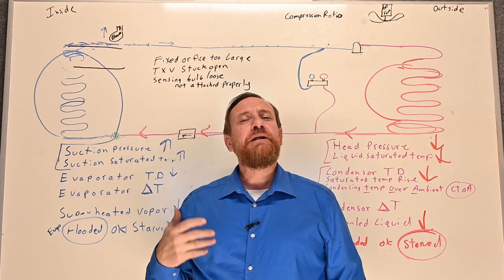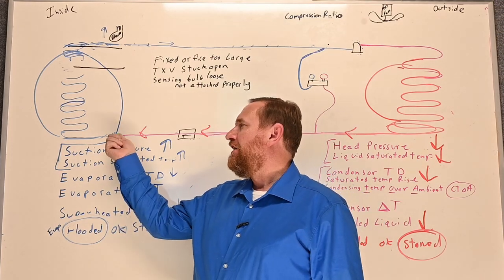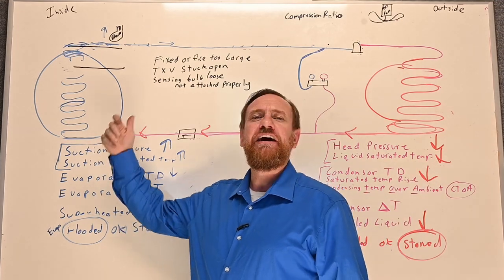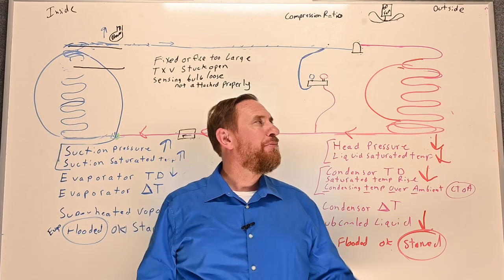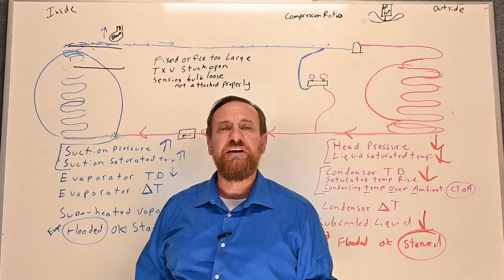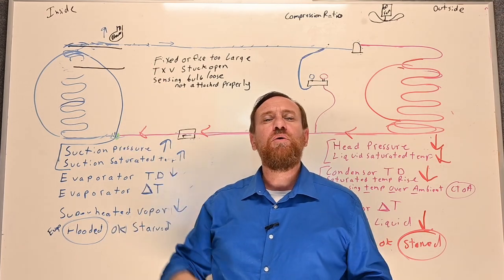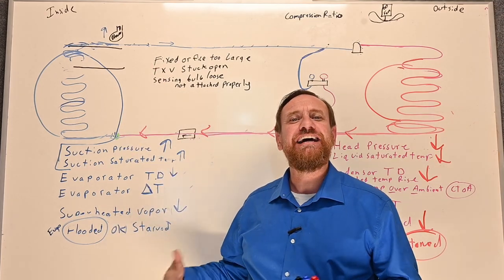And I've seen this done by accident. Somebody simply changed the evaporator coil or they changed the condensing unit and they left whatever metering device was with the evaporator coil instead of putting the metering device that matched the compressor. And because it made noise and blew cold air, they thought, well, it works. Well, it wasn't working because I had to go out and fix it.